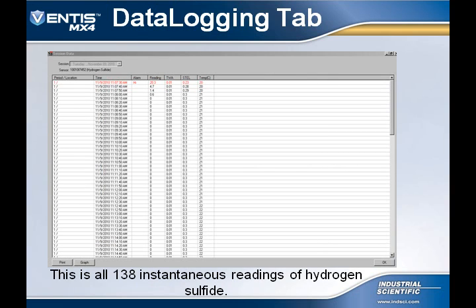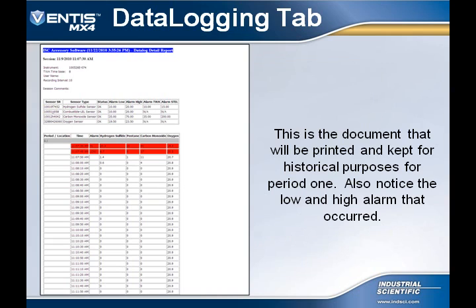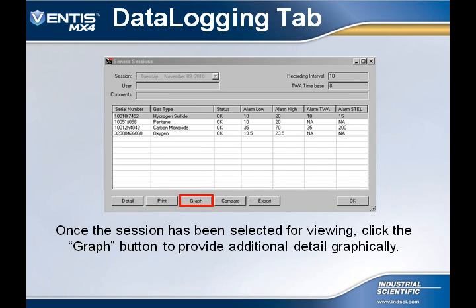There are 138 instantaneous readings that have been recorded. This is a list of all 138 instantaneous readings of hydrogen sulfide. Notice the very first reading is in red, which is an indication that the instrument was in alarm condition. The user can select the Detail button to look at all 138 instantaneous readings. Selecting the Print button will print a hard copy document for period 1. Notice again that the first two readings show the instrument was in an alarm condition.